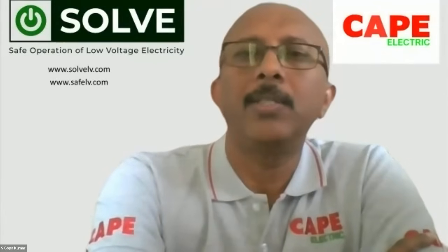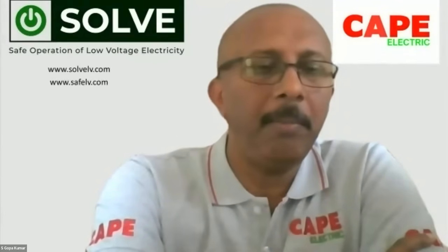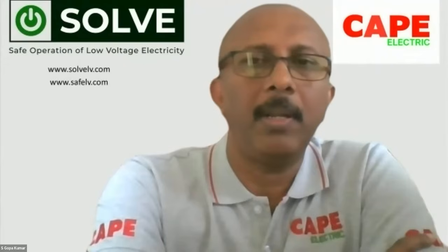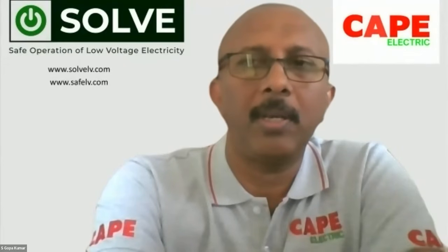Pradeep Shah is asking, would like to know the impact on safety due to aging factors in MCBs and wires. What is the age normally you recommend for wires and MCBs? In a properly designed and installed electrical installation, it is a minimum of 20 years. But this minimum is not the average. The minimum is 20. It can be an average of about 30 years. And if you are maintaining it with correct periodic verifications, then it can go even up to 40 years.